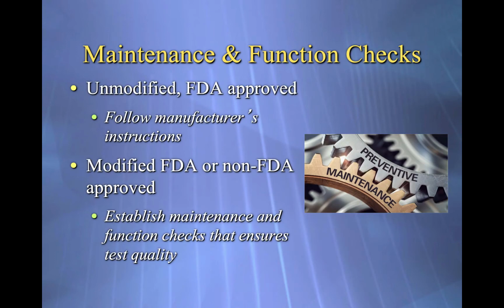Okay, maintenance and function checks. If it's an unmodified FDA-approved test, you follow the manufacturer's instructions. That's all you're required to do. If it's a modified FDA or a non-FDA approved, so a home brew test, then you must establish maintenance and function checks that ensure test quality.